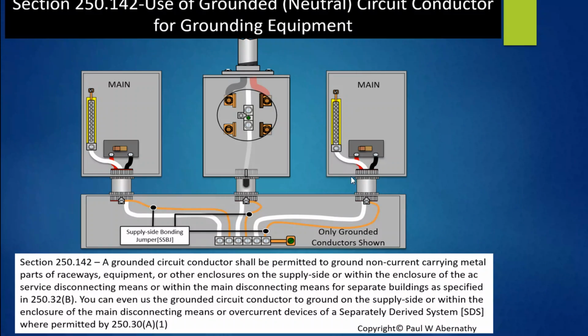This one right here, using, say, concentric, eccentric knockouts, then they're considered impaired knockouts. I have a bonding bushing with a bonding jumper based on the size of the conductors that are supplying this enclosure. Now, here's the main bonding jumpers, which are required in the service equipment. These are both service equipments. They are grouped together in one location. If this was factory installed, no sizing. If this is a wire, I would have to size it based on the size of the conductors that are supplying this service equipment. Okay, pretty simple concept here, right?